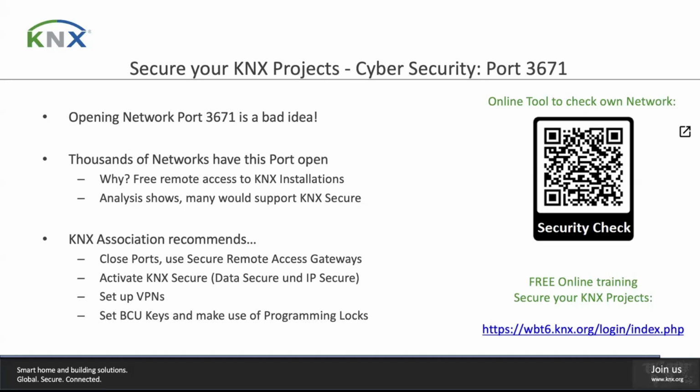I'd recommend, if you're going to use BCU keys, make sure that BCU pin is inside somewhere like the panel. So if anyone else comes along and needs to do anything on that system, they've got it to hand without having to dig through loads of documentation to find it, because it's the sort of thing that you may come back to 5 years down the line and not know. Somewhere like inside a panel is probably secure enough, but it depends on your installation.